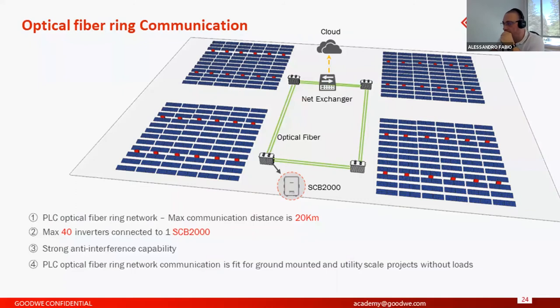So the other possibility also is for big plants and utility scale with fiber optic communication between the SCB2000, for example, because it's starting with the power line communication, and then the internal, so you can put the optical fiber. So the SCB2000 is the one communication that can use also the typical optical fiber. So you can increase the communication distance to 20 kilometers, for example. And this option, SCB2000, is only for max 40 inverters. Okay.